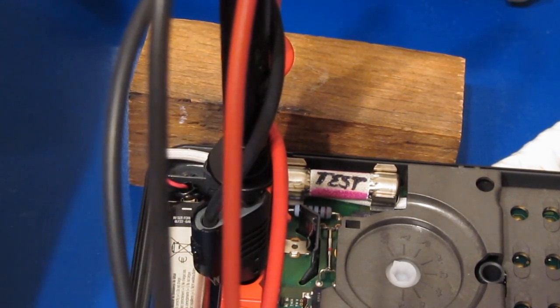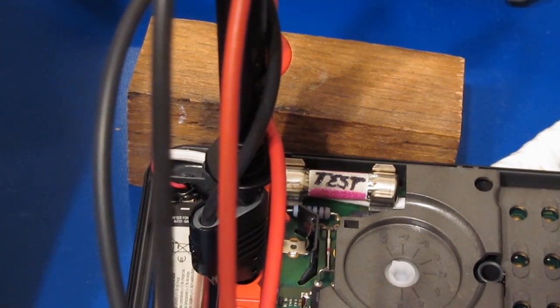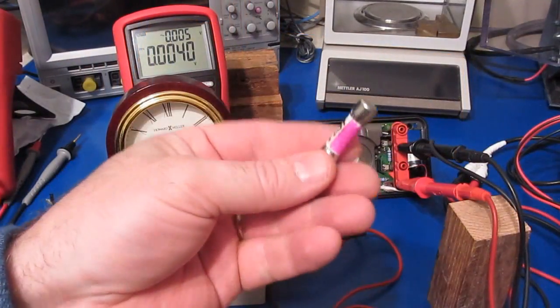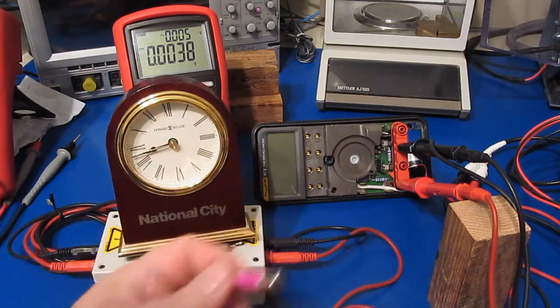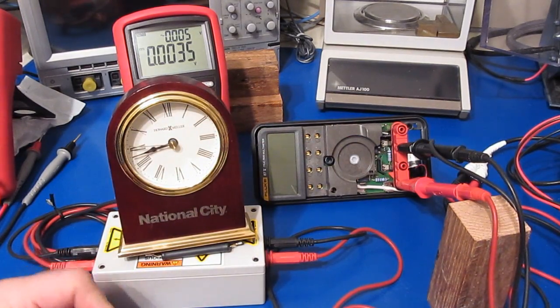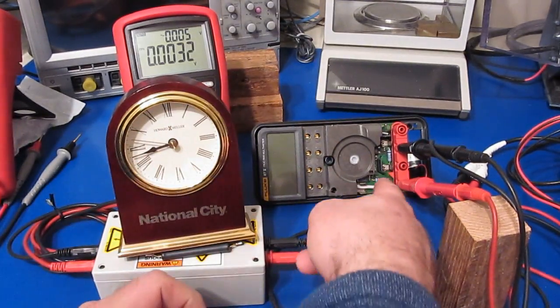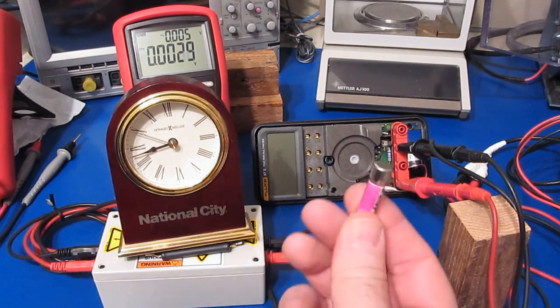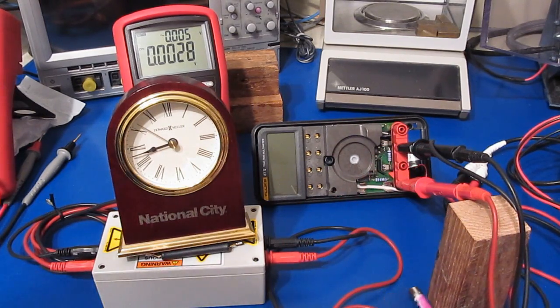It definitely looks like it's arcing right inside of the fuse. So all I've done is just remove the fuse. I can't really tell if this was arcing from here down to our wire underneath, or if it's actually arcing inside of the fuse, so let's just try to run it without the fuse.